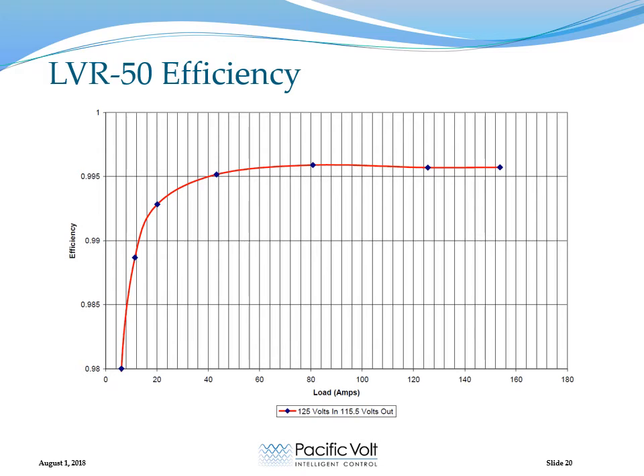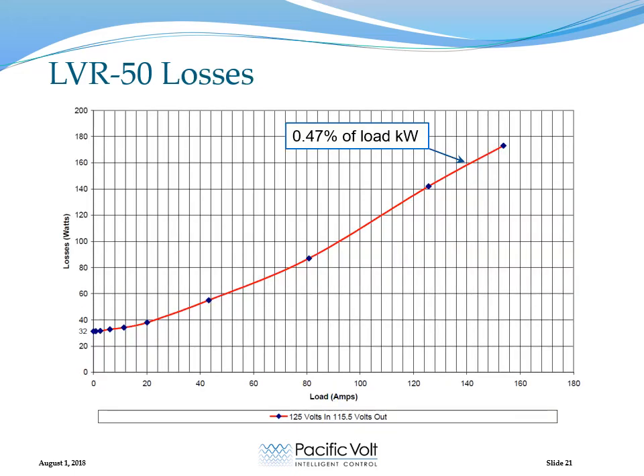This is the efficiency curve of the regulator, and you can see that it very rapidly exceeds 99% efficiency. For the most part, the regulator operates in this range where the efficiency is in excess of 99.5%. This is an alternative way to plot efficiency. Here we're plotting losses as a function of the load current, and the losses are typically less than half of 1% of the load current. The regulator itself, with no load, draws about 32 watts of power. It's extremely efficient, and it appears as a 0.5 kVA capacitive load to the network.